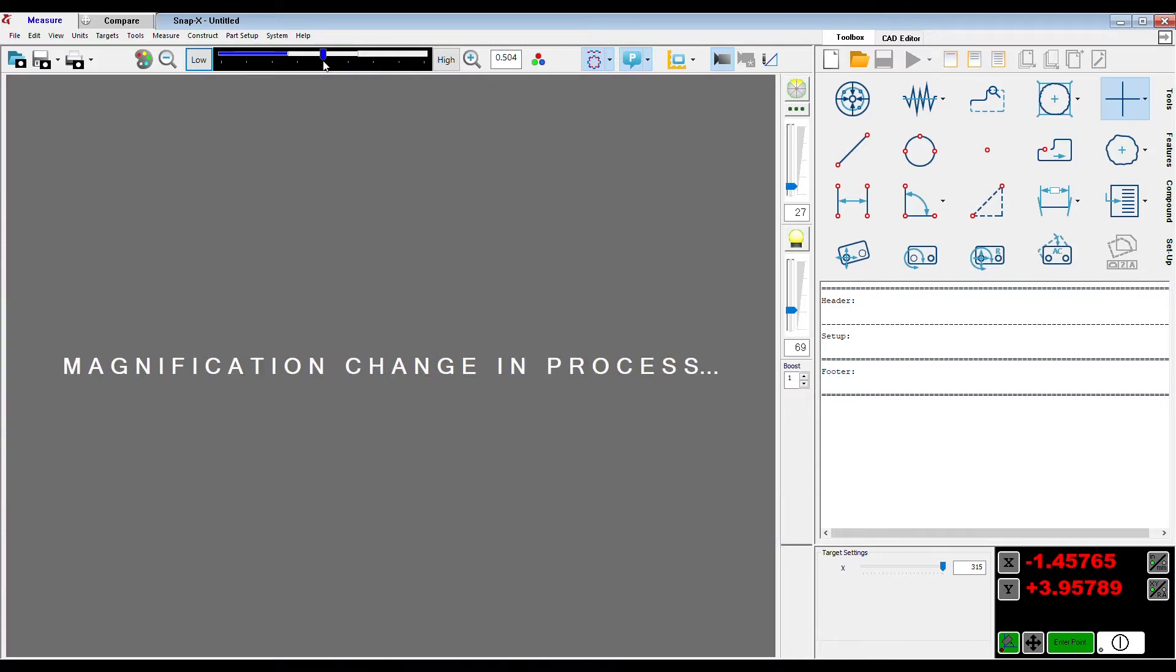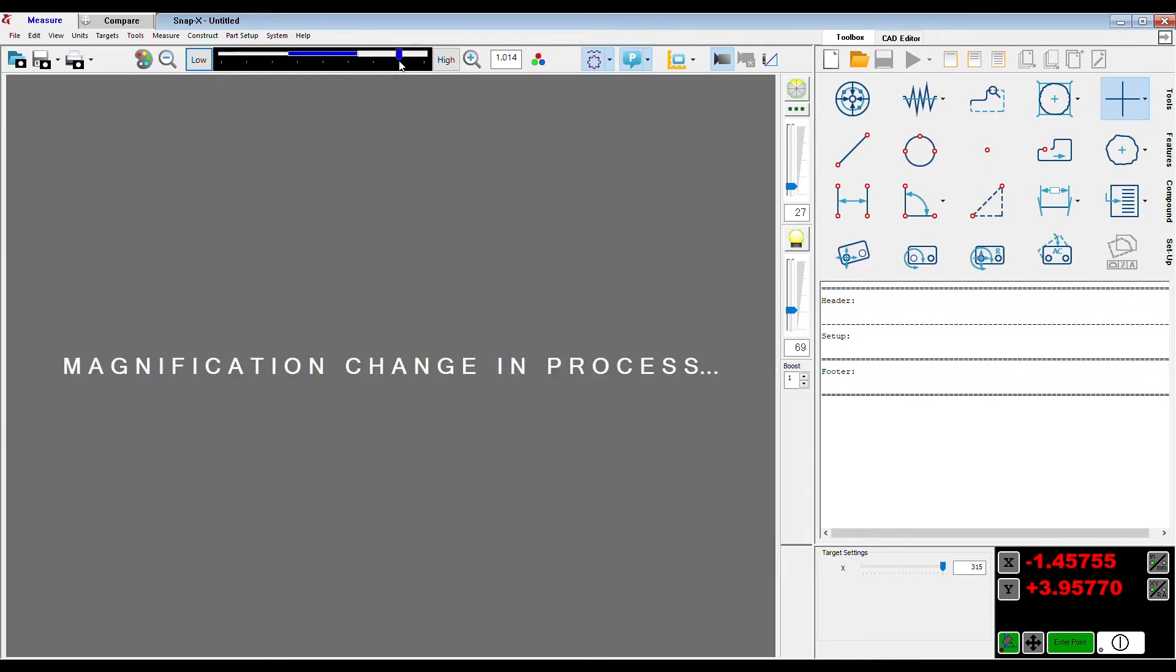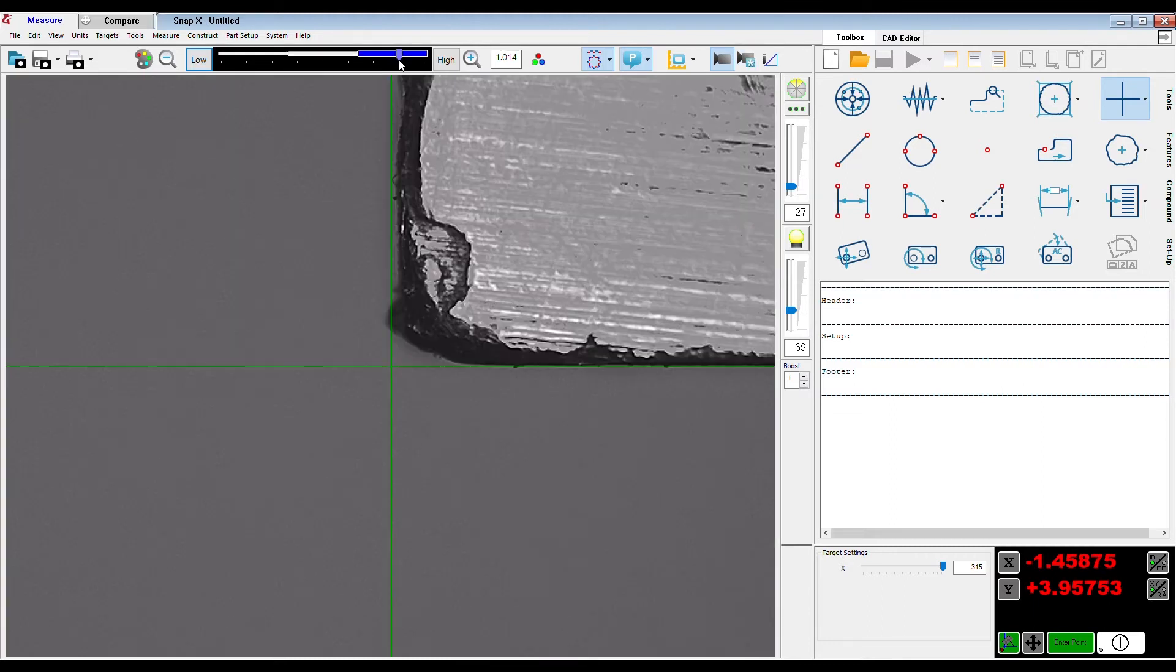Before this innovation, operators were required to manually unscrew a lens, attempt to safely store the lens, screw in a new lens and recalibrate, a very timely task that could never be done in the middle of a program.